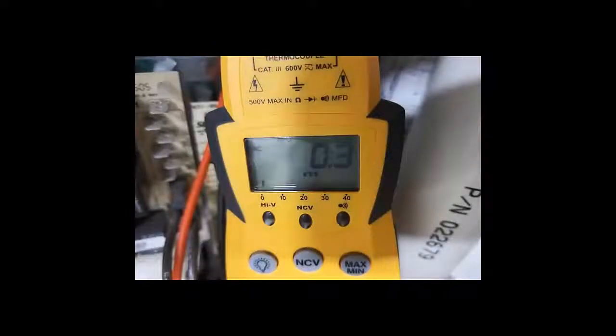Now, some silicon nitride igniters only require 30 to 40 volts to work properly. So you want to make sure that you're familiar with the equipment you work with and the type of igniter it uses. If you get no power or a power reading significantly out of range, you have either a main power problem, a bad circuit board, or bad wiring between the circuit board and the igniter.